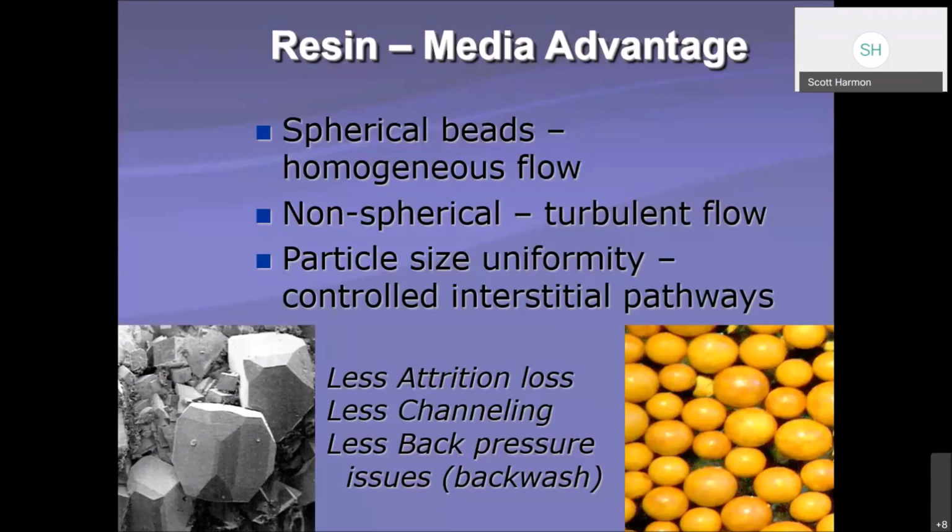You get less loss through washing because of the inherent shape and density of these medias. Less channeling, which means simply that because of their shape and the way they form together, there's less of an issue with a channel opening up in your filter. Like in old school filter terminology, you wouldn't have a boil in those filters. Less back pressure. I don't know if that's always true during the backwash, but it may be because of the consistent size that the bed rise would be a little bit easier. But again, I'm not sure that's always the case with these types of resin medias.